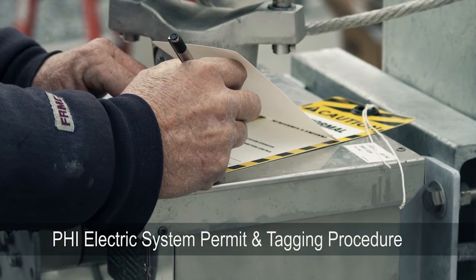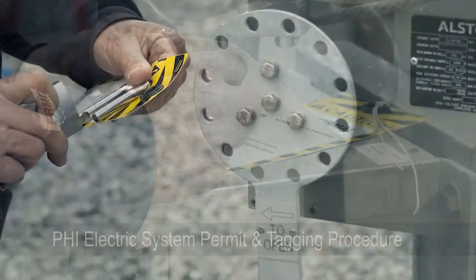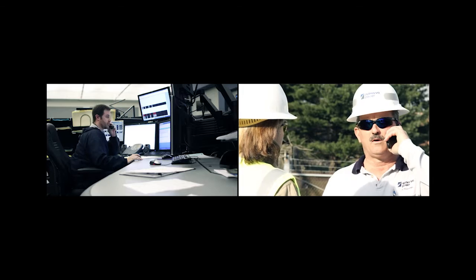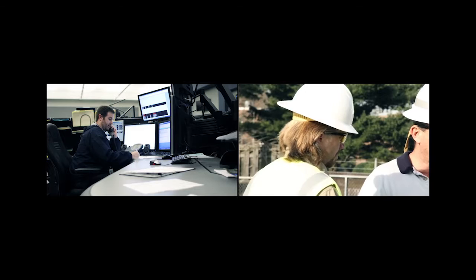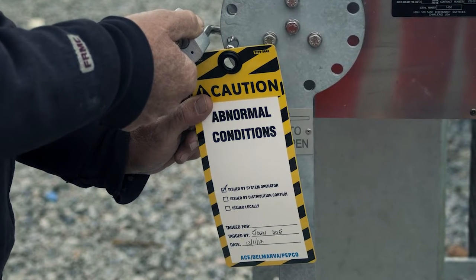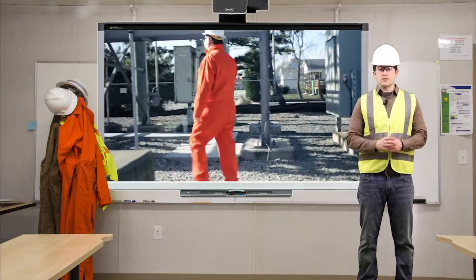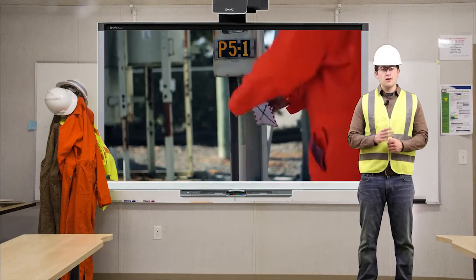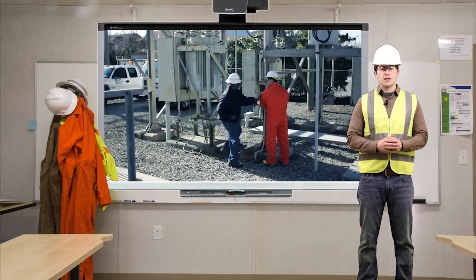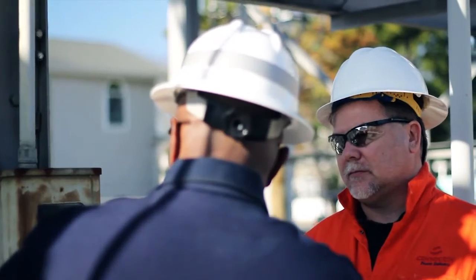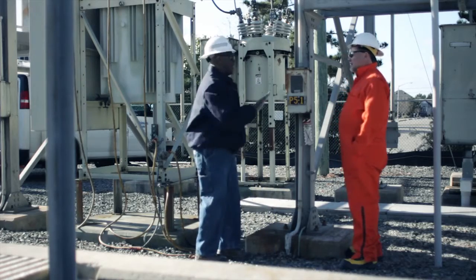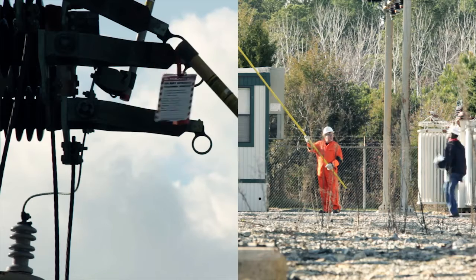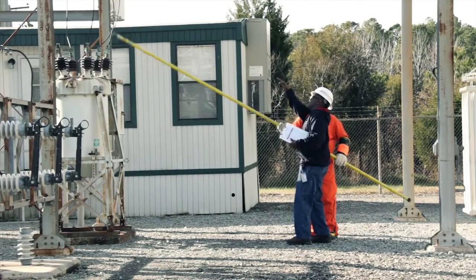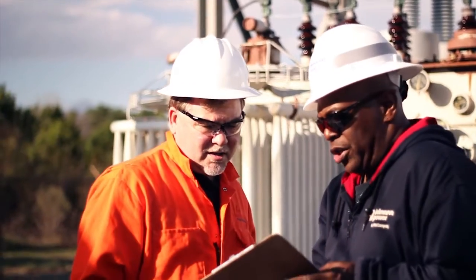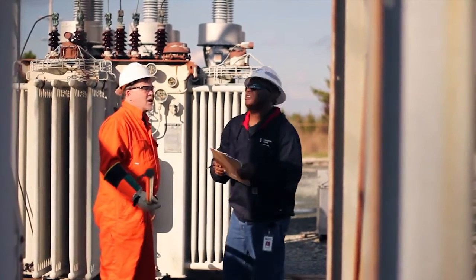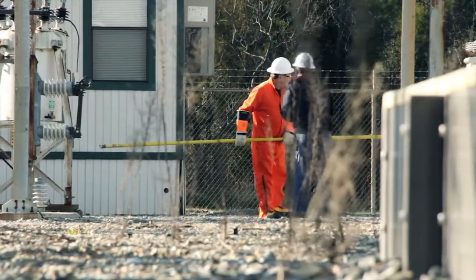The PHI Electric System Permit and Tagging Procedure specifies how personnel can obtain permits, apply tags, and what tags must be used. Additional specifications include the communication which must take place between field personnel and the control center personnel, how tags must be applied, and how and when they can be removed. No person shall remove a danger or caution tag from any circuit control point, blocking point, switch, or other piece of electrical equipment except when directed by the appropriate system operator. And they must be an authorized individual according to the PHI permit and tagging procedure. No person shall operate a switch, disconnecting device, or other piece of electrical equipment which is blocked unless directed by the appropriate system operator, and they must be an authorized individual according to the PHI permit and tagging procedure, and only after all danger tags have been removed.